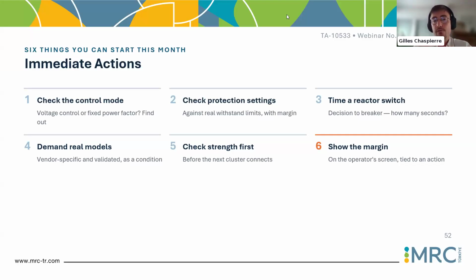To anticipate this kind of event, you also need to run studies. And it's important, as I said, to use the proper software, EMT. With more and more power electronic converters and weaker grids, you need EMT. But EMT is not enough. You need to make sure you have accurate models as well. To have accurate models, they need to be vendor specific and they need to be validated. Validation is very important.